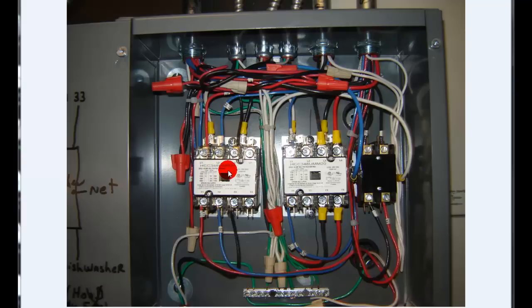It also has a set of auxiliary contacts in here, dry contacts that will be operating the shunt trip breaker. It'll send 120 volts back to the shunt trip breaker which has a magnetic coil in it. So when the power is sent back to it, it actually trips a breaker and cuts off the power to all the equipment that's underneath the hood.